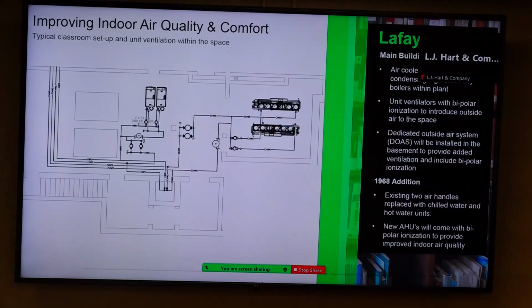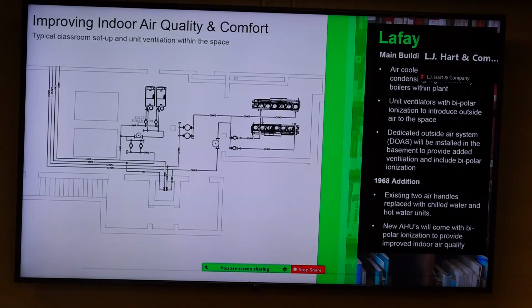Any questions on the generalized scope of work? I know we talk fast, but let me know if you have questions. Really, the main concept is getting away from individualized units per classroom and having a centralized plant provide the heating and cooling. In the classroom space, you'll have variable air volume units or unit vents, depending on the space, providing outside air into that space as well.